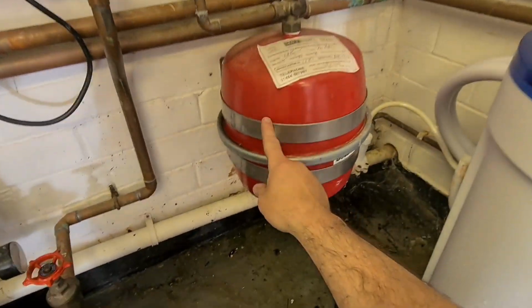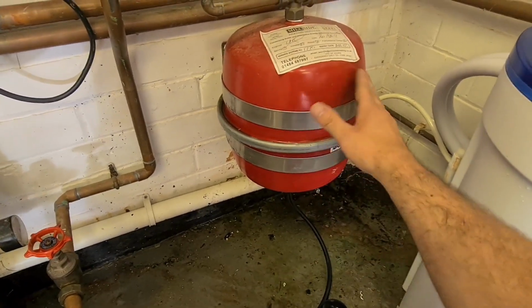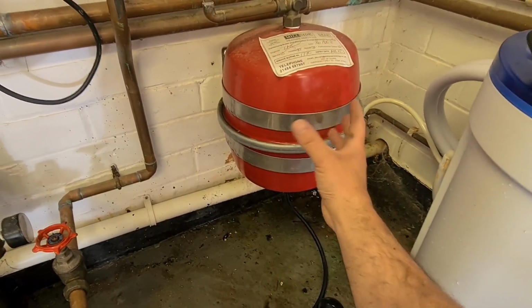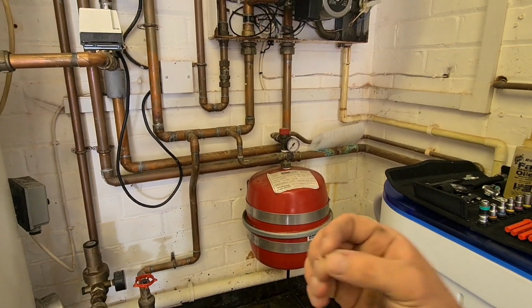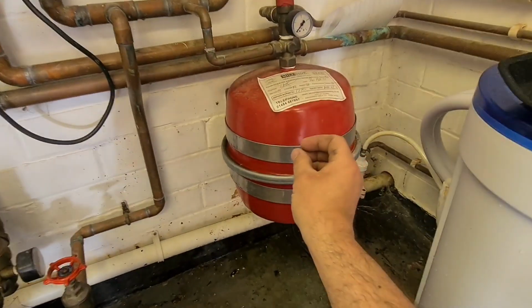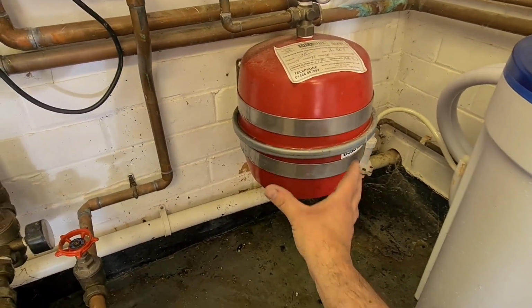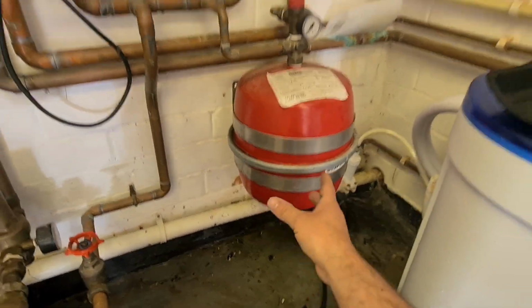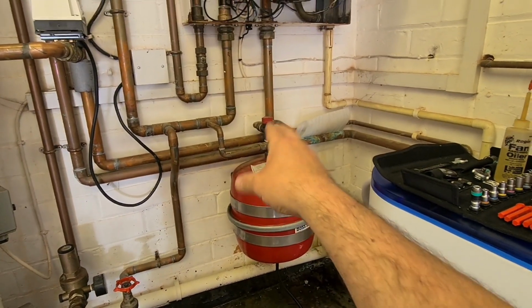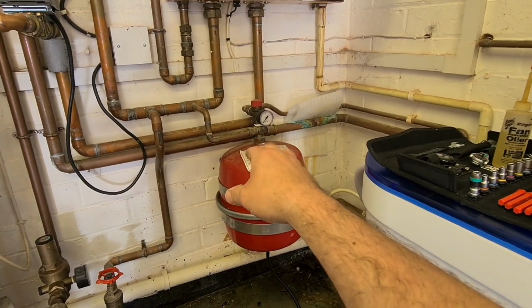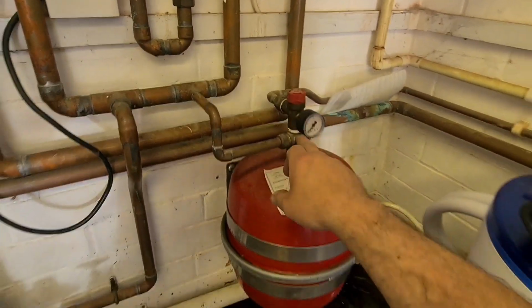So what this expansion vessel does is, as this boiler heats up and heats the full building, this has a balloon, a rubber membrane inside here like that, that's basically a pocket of air all the way around it. As water heats, it increases in volume, so the bag will expand and compress against the air in there. I've got a feeling this has been discharged, so I'm going to whip the pressure relief valve out as well, just to make sure that's seating okay. Fine.